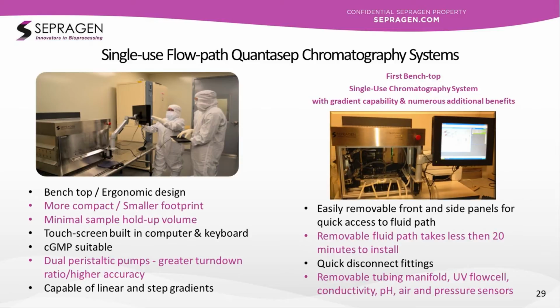And then these are bench scale systems. This is our bench scale single-use chromatography system. You can see that we have removed the outer skins, which are very, very easy to remove. So these are just stainless steel removable panels. And inside that are pinch valves and flow path tubing and sensors. And so the flow path is neatly laid out inside the machine and can be easily removed within 15 minutes. And we say here removable flow path takes less than 20 minutes. We've actually clocked people following our instruction doing it in 14.5 minutes.